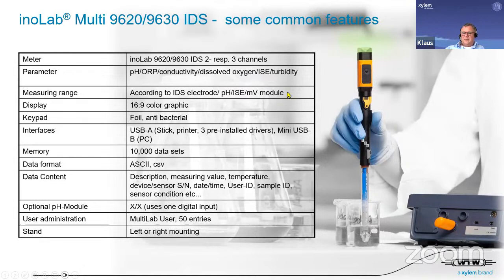Then if you're asking about the measuring range of these meters, of course, none of them, neither the handheld nor the benchtop meters, have a measuring range because the measuring range will be supplied by the IDS electrode. This is the measure of the measurement. This is what the IDS electrode delivers. This will be displayed.